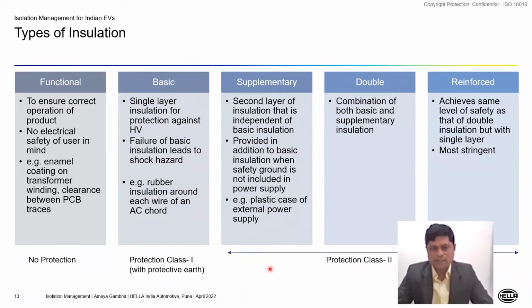But whenever there is no earth terminal available for protective earth, then we need to take help of additional or advanced layers of insulation. So supplementary insulation is basically one additional layer of insulation which is independent of basic insulation.